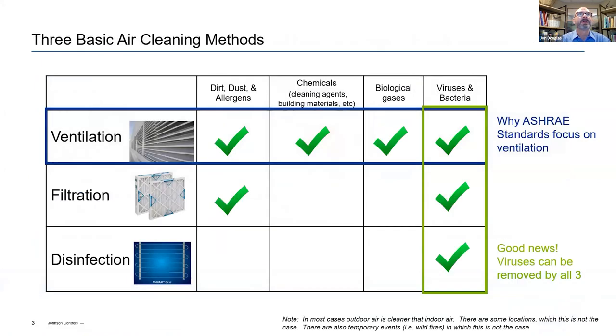First thing I want to talk about are the different air cleaning methods. If you think about air cleaning, we can break them down into three basic methods. The first one is ventilation, where you dilute the pollutants in the air with fresh, clean air from outside. Filtration, where we mechanically remove the particles in the air and take them out. Or disinfection, where we actually deactivate the bacteria and viruses in the air. They each have a different effect on the different pollutants in the air. Ventilation tends to be preferred in a lot of the ASHRAE standards because, by the nature of it diluting, it actually addresses all the pollutants in the air. It takes care of dust, chemicals in the air, the biological gases in the bathroom, and the viruses and bacteria.